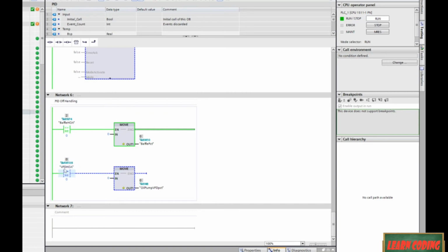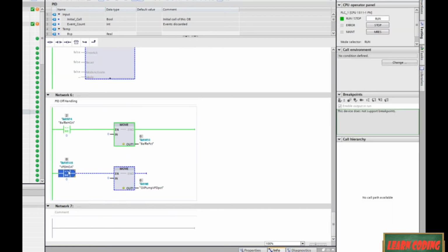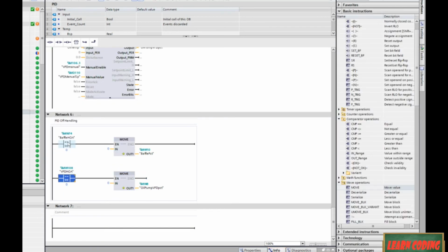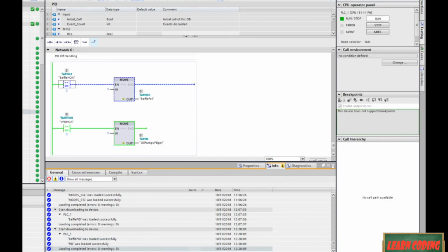This is supposed to be looking to see if the baffle HOA equals 0, which means off, and not if it's not equal to 0. So it looks like we were overwriting. What did I just click on? I mean, come on, Control Z. That's not what I clicked. These shouldn't be not equals. These should be equals. So if these HOAs are equal to 0, then we should be writing out a 0. So let's go ahead and dump that in, and let's see how this thing looks now.